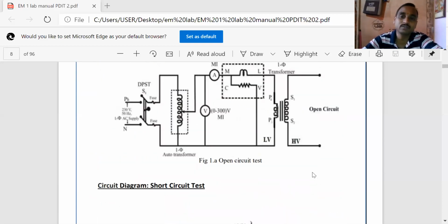The open circuit test uses the no load readings: V naught, I naught, and cos phi naught. From this, you need to find out the core losses in the transformer. There are two types of losses. One is core loss, and the other is copper loss. Core loss is called the no load loss, and copper loss is the winding loss under load condition. So the open circuit test gives the core loss, and the short circuit test gives the copper loss in the transformer.